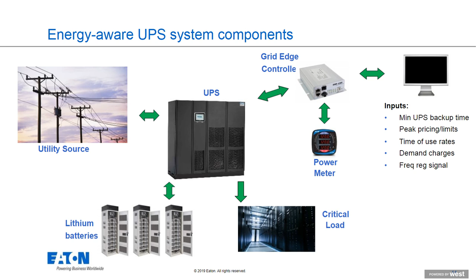So in an energy-aware system, there's 3 operating modes. And the one on the far left is very traditional UPS operation. Rectifier converts AC to DC. The inverter goes back to AC, supports the critical load. The battery is fully topped off and charged. And the static switch on the top there is off.